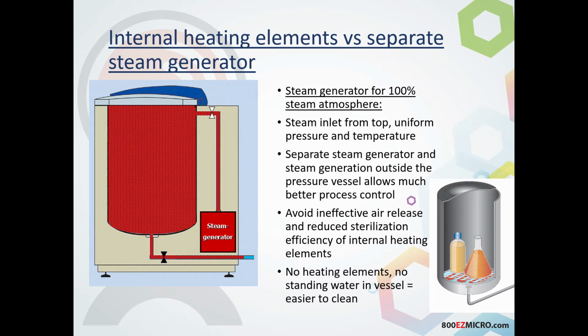inside of the unit. Also, if you are reusing water and it's recycled, that goes back into your autoclave, so you use water that's in the bottom and then it comes back in, all of the materials that could have boiled out of your liquids boil right into that water. They stick onto the heating elements. Then we've created an area where it's going to create burning, and then your heating elements are going to burn out as well. So not only is it inefficient, it's also fairly dirty, and it's also not a very good way to maintain an autoclave for a long period of time, as you will be replacing those heating elements at some point.